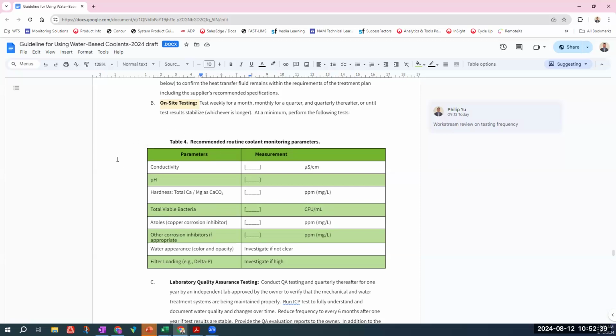Philip, the only question I have, just because I'm intrigued, is how often do you think you'd have to touch a water-based system to add additives to keep it in spec as a result of this testing? Like, is it normal to do monthly? Is it quarterly, yearly? Usually the vendor has an automatic feed system. It's a storage tank for the coolant. It gets triggered automatically, and in my experience, it will get triggered at least monthly. If there's no water loss, when they pull the liquid out for testing, it will trigger a refill. But it'll be a small amount.